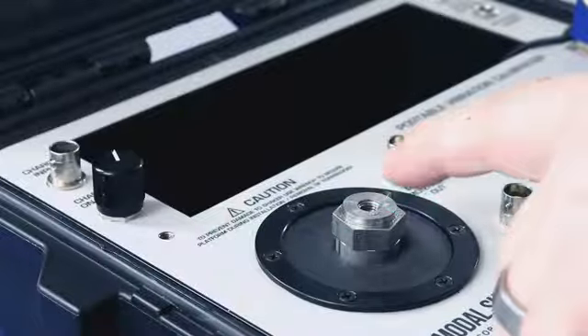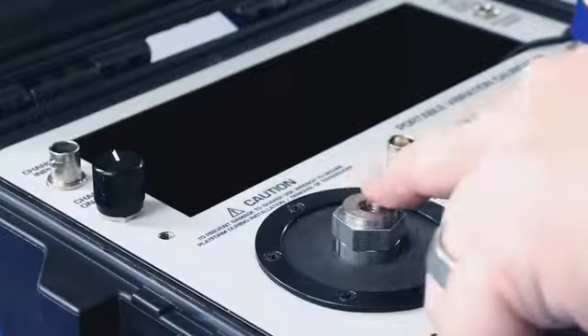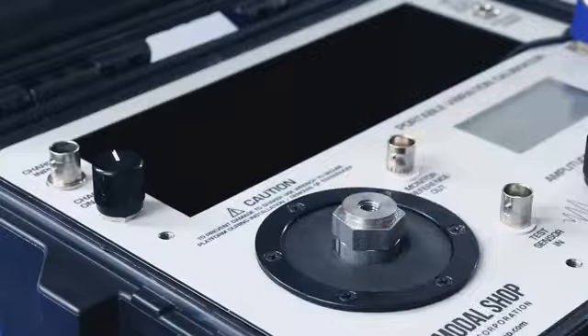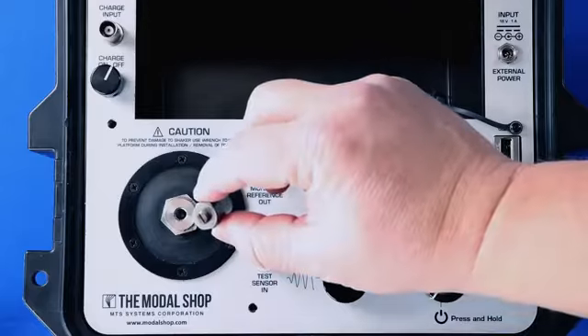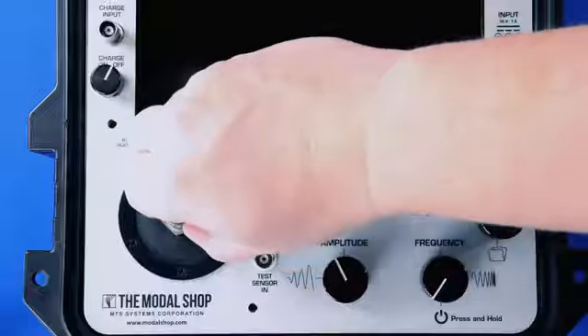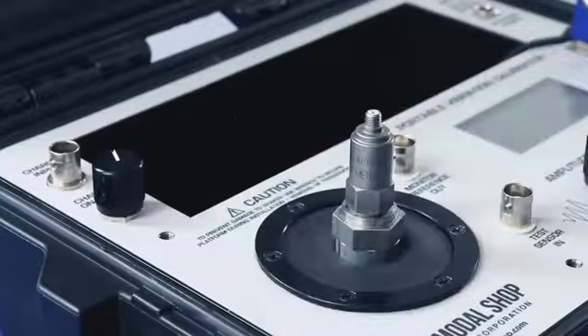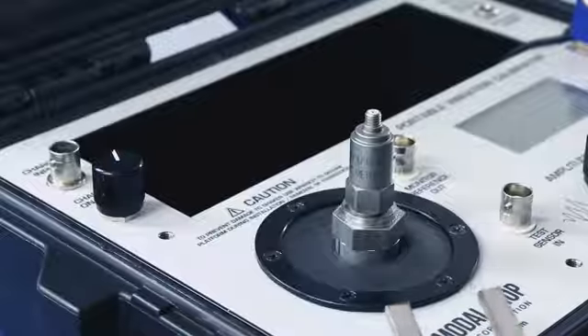We use Dow Corning DC4 on the top of the shaker. We want to make sure it's clean, make sure the grease is applied, and we want to make sure that the bottom of our transducer is clean. And then we can screw this onto the top. I'm using a 10-32 to 1/4-28 stud, as the shaker has a 1/4-28 female hole.